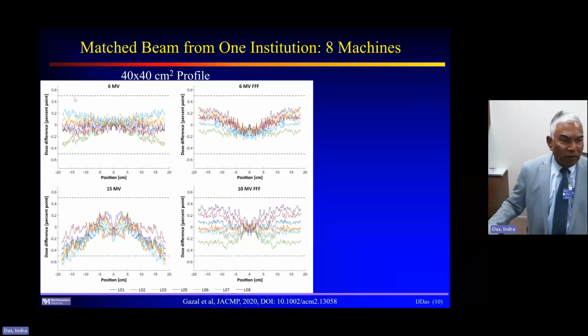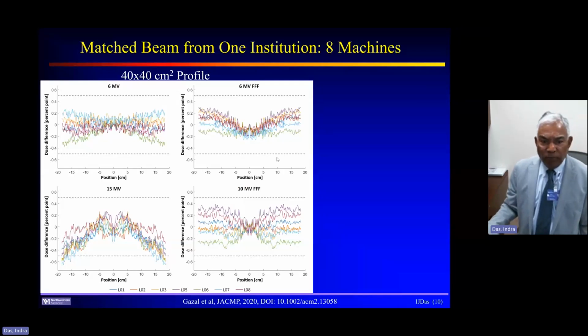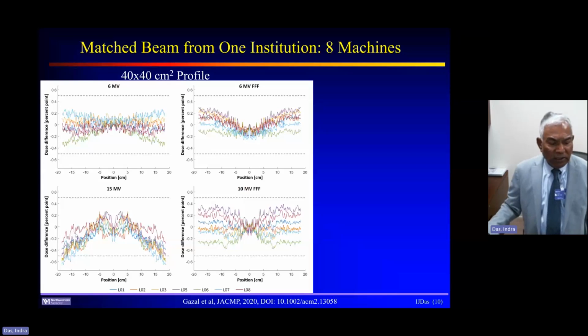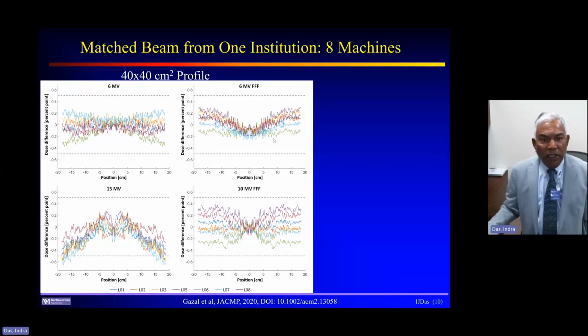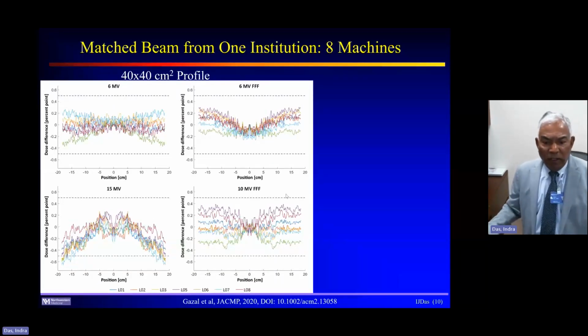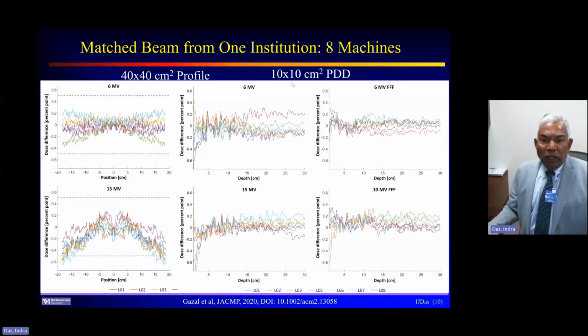Obviously, these are all 0.4, 0.4. These lines which you see are plus or minus 0.5. You see that the entire data sets are within plus or minus 0.5% in these institutions for the 8 machines that they compare, and for the 6 MV beam, 6 FFF, 10 MV, 15 MV beam, and 10 MV FFF. So there's not much difference. I mean, they are within the bound of plus or minus 0.5%. When you look at the 10 by 10 field, those differences disappear even faster. If you look at the 6 MV beam, the differences are within 0.2%. FFF is also plus or minus 0.2%. So there's not much difference.